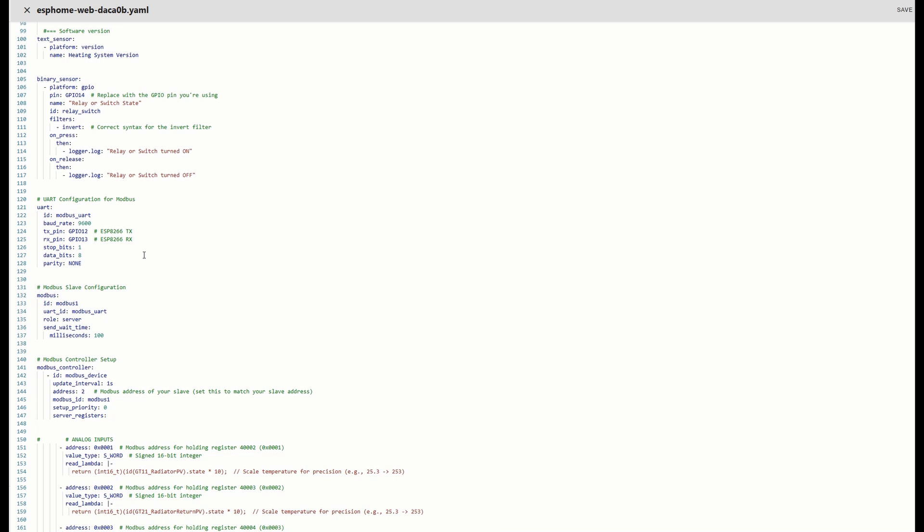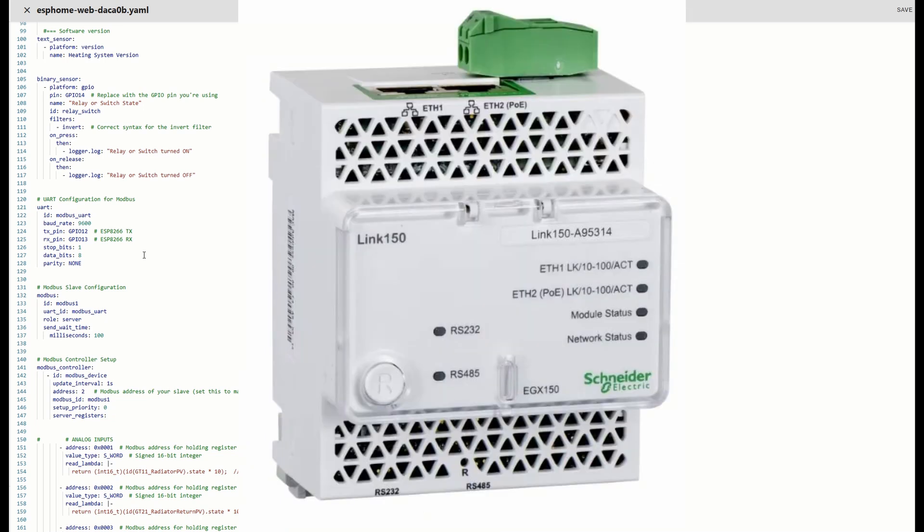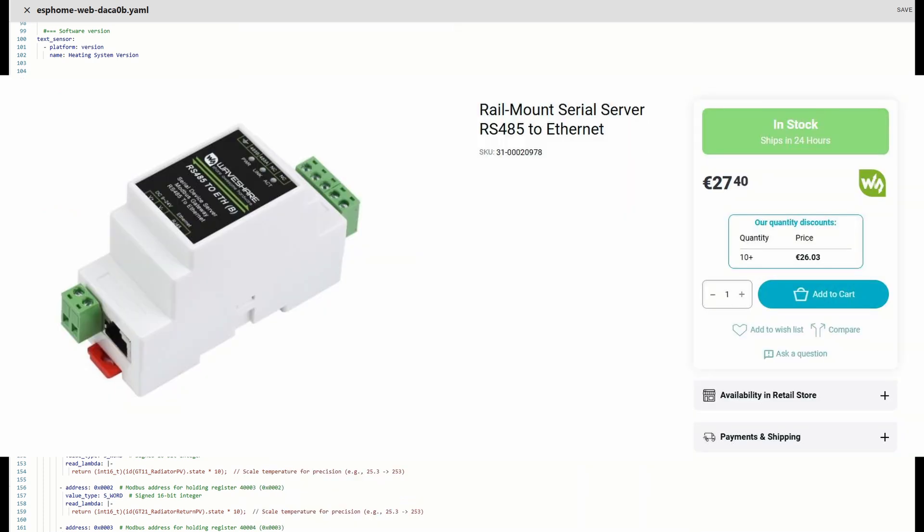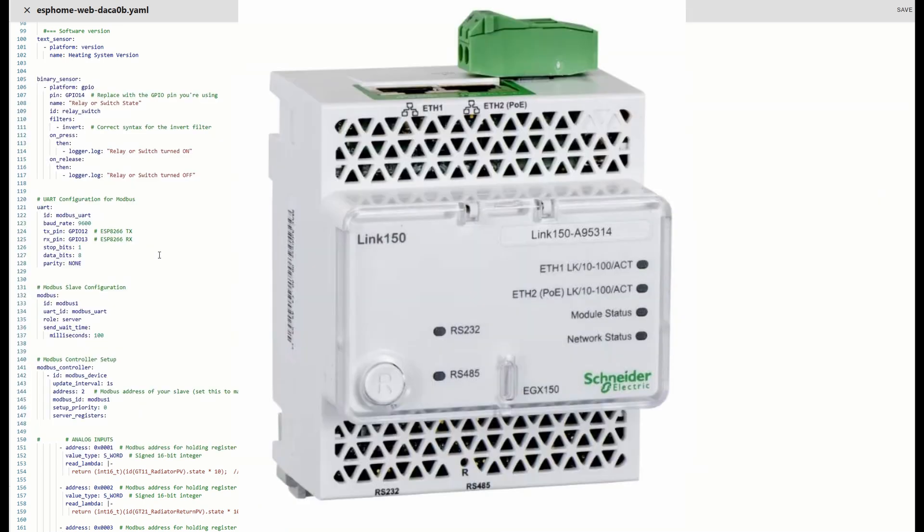As a Modbus master, like I said in previous video, I'm using my Schneider Electric Link 150 to convert RS-485 to Modbus TCP IP. While this device is reliable, it's not cheap either. There are other variants of serial to TCP converters out there. I just happen to have this one, so I am using it.